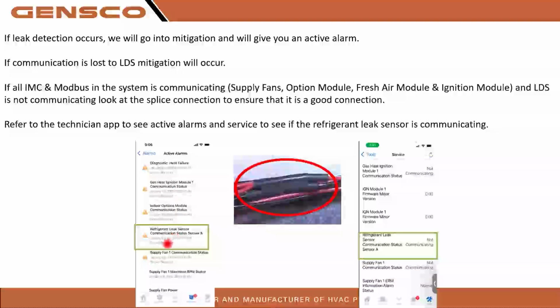So if we see an alert saying refrigerant leak sensor, where are we going to start our diagnostics? We're going to start at the sensor to see what's going on. They have these splices in there. So if it's not communicating, look at the splice connection and ensure that it's got a good connection. Now, there were some weird ones up in Alaska where we had some condensation and then freeze. So it started to freeze and the condensation kind of peeled that apart because ice got underneath there, and there was an open hole to atmosphere. So we were freezing in there. Refer to the technician app to see active alarms in service to see if the refrigerant leak sensor is communicating. So again, a lot of different alerts prompt us to concentrate wherever the diagnostic is needed.